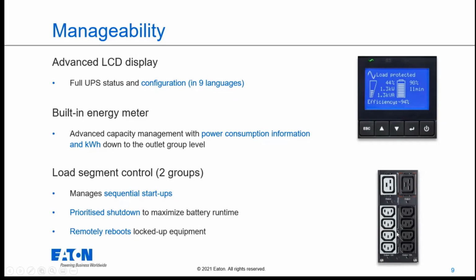And we have the load segment control. For those not aware, we have two groups - the outlets marked in white colors, group 1 and group 2. With those groups you can manage sequential startups. You can decide to start group 1 six seconds after the mains, and then group 2 six seconds after group 1, so you can sequentially start the load - for instance, to start the switch before you start the server, so you are sure the network connection is up and running when you start the server.